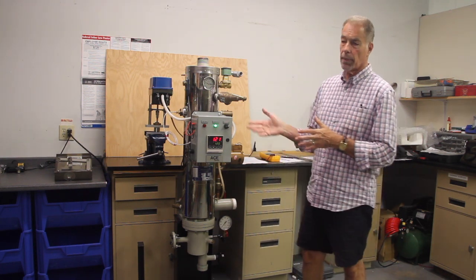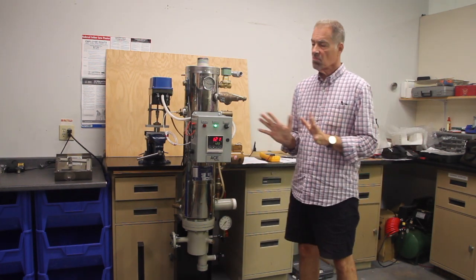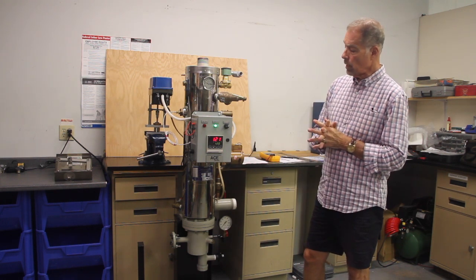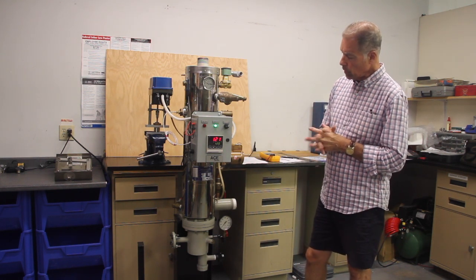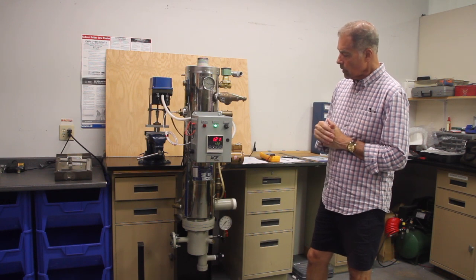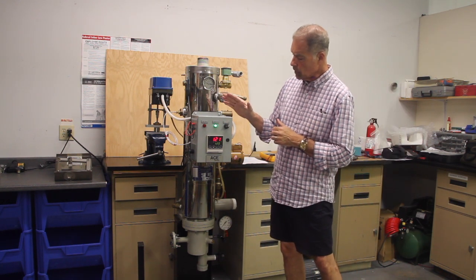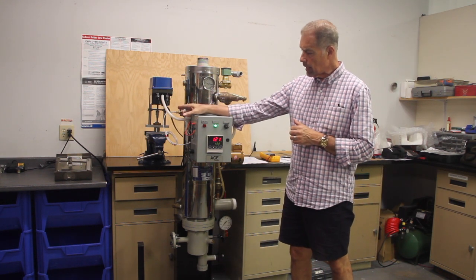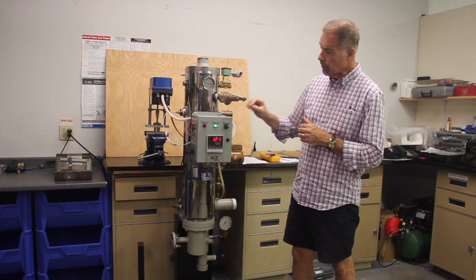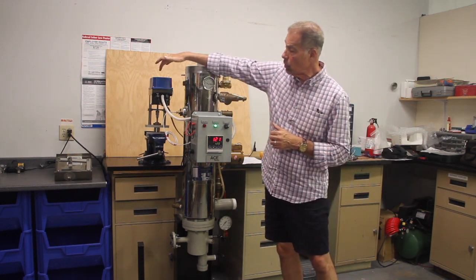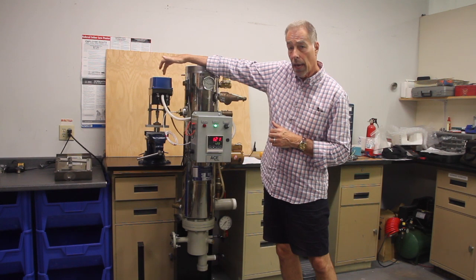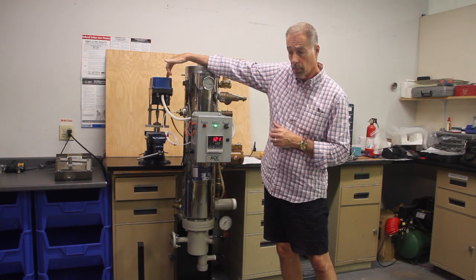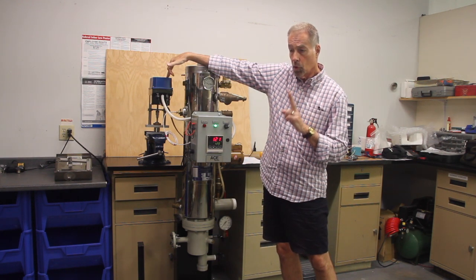We've had almost no problems at all. If you get a lightning strike, it might burn up the controller, but other than that, we've had very little problem with the controllers. We're going to go through the controller in a minute, but what this controller does is read the water temperature, as I said, and then put out a 4 to 20 milliamp signal to this valve actuator.